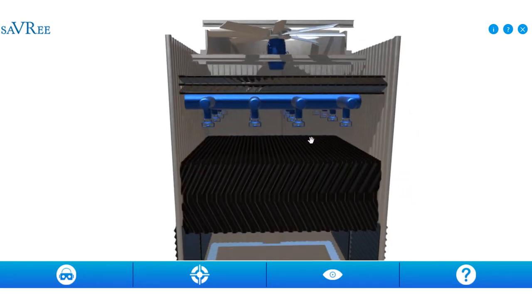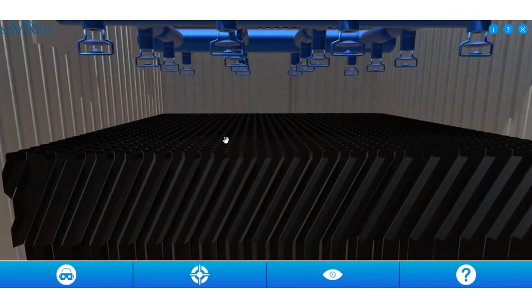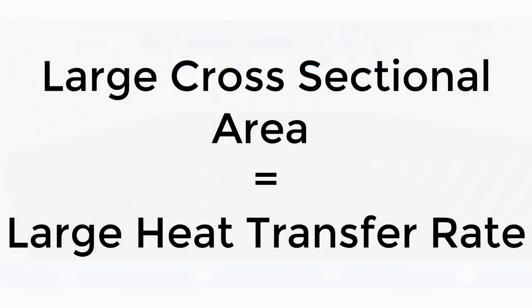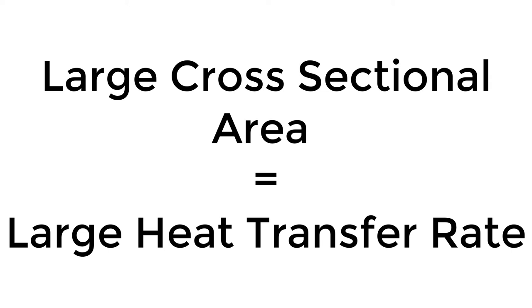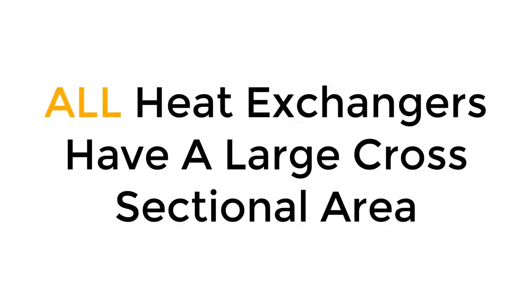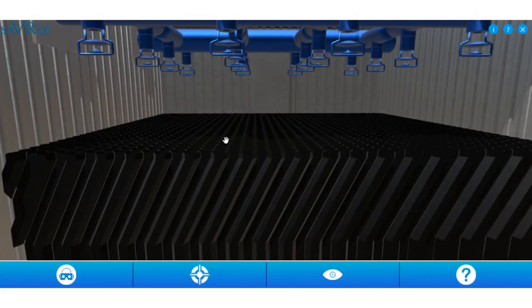The fan creates the movement of air. The water comes out the nozzles and trickles onto the heat exchanger. Because of the shape of the heat exchanger, we spread the water over a very large cross-sectional area, bringing it into contact with the air. There's no point sending a two-inch pipe full of water down through the cooling tower — the air can't do much to cool it. But by spreading it over such a large area, the air takes away as much heat as possible in as short a time as possible. That's our cooling effect.